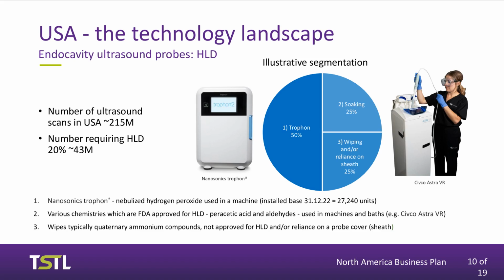and it is high-level disinfected. The other 2 methodologies that are commonplace in the United States, and we believe they account for pretty much 50-50 of the remaining scans that are not undertaken in Trophon, are either achieved by soaking the probe and transducer in a liquid chemical. There's a picture on the right-hand side of a product called Astra that is manufactured by a company called Civco, and you can see the healthcare worker is loading the probe into a chamber inside that box, and inside there is a liquid. It probably will be peracetic acid, and the instrument will soak in there for a period of time, can be as long as 10 minutes or more before the probe is taken out and then has to be rinsed before it comes into contact with the next patient.